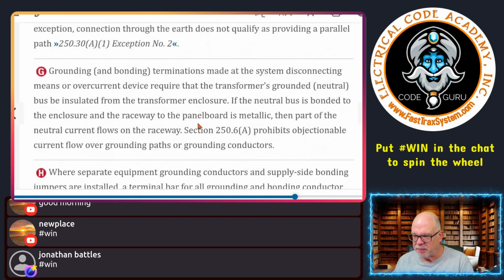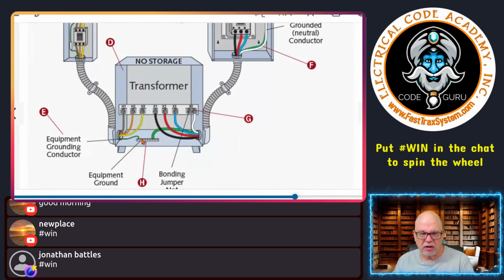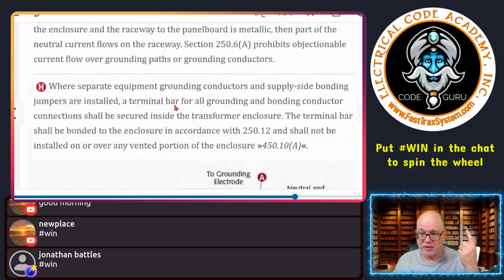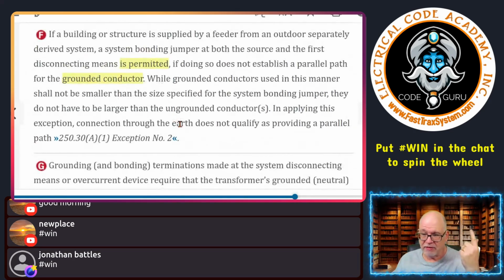Okay. So I don't have a picture to show this, but if this transformer was outside, we're talking about this grounded conductor right here. Now, first of all, it has to be sized to handle the load, right? We know that. That's the first thing. And we know, secondly, it can't be smaller than the size specified for the system bonding jumper, which is still going to be based on 250.102(C)(1), based on the derived conductors.